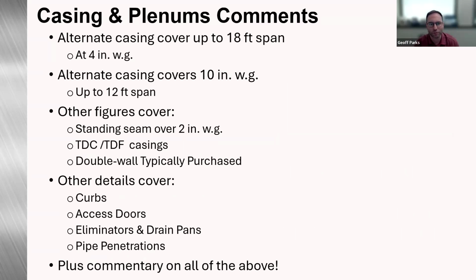Some additional comments. The alternate casings cover up to 18-foot spans at 4-inch water gauge. The alternate casing covers 10-inch water gauge up to 12-foot spans. Other figures within the chapter cover standing seams over 2-inch water gauge, some TDC, TDF casing constructions, and double wall, which typically is purchased, but there are fabrication details in the standard. Other details cover any curb, access doors fabrication, eliminators and drain pan fabrication. There are also pipe penetration details within that chapter as well, plus commentary on all of the above.